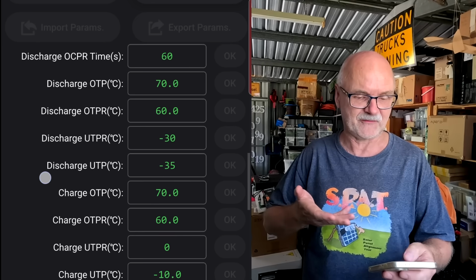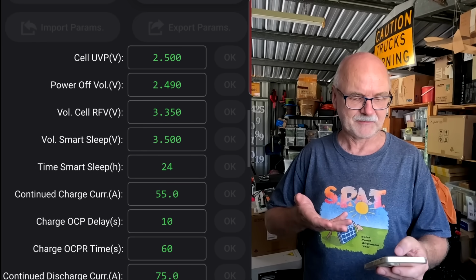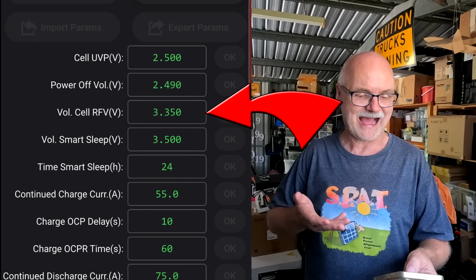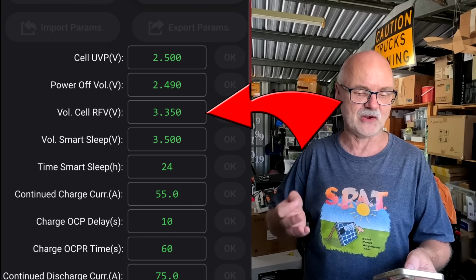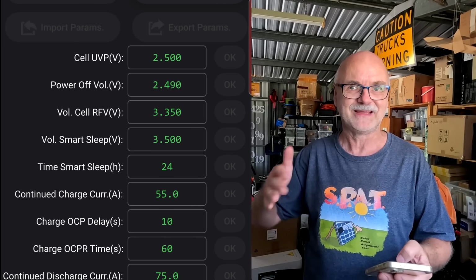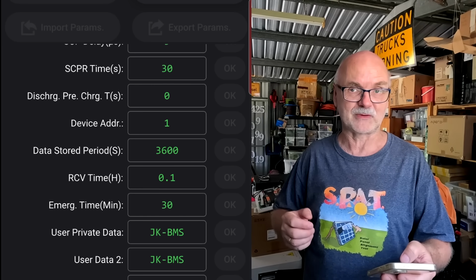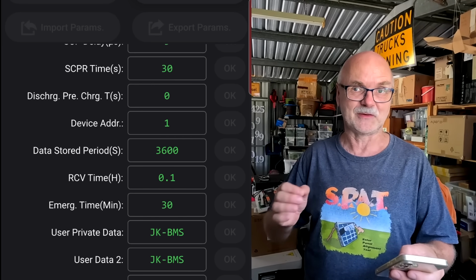Whatever we have set here in this device, there it is, voltage cell, RFV, the requested float voltage, is 3.35 times 16, falling back to 53.6 volts after this 0.1 hour.